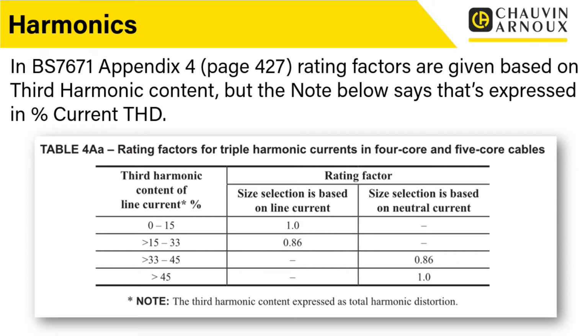So rather than just looking at how much is in the third harmonic, or even how much is present in tripling harmonics, the multiples of 3, what we're actually doing is taking percentage THD, which is the total harmonic distortion, not just that from the third harmonic. So there's a few things going on. In the previous slide, we're correcting the line current based on the total harmonic content. And then we're applying a correction factor based on that content again, but for the tripling harmonics. And this is really to have the knock-on effect on the size of the neutral conductor, and making sure that the additive effect of the tripling harmonics is accounted for.